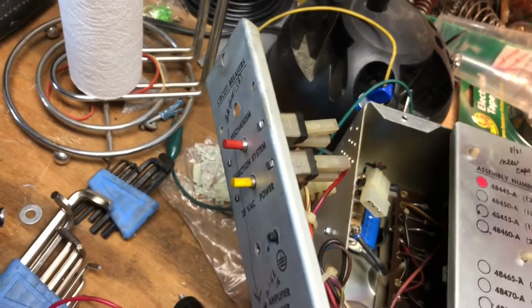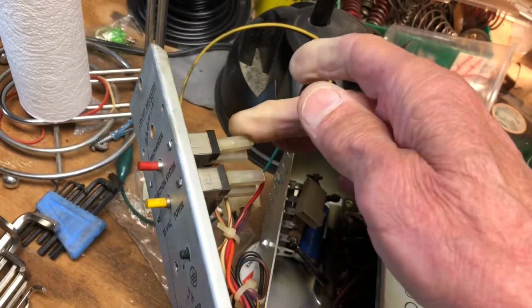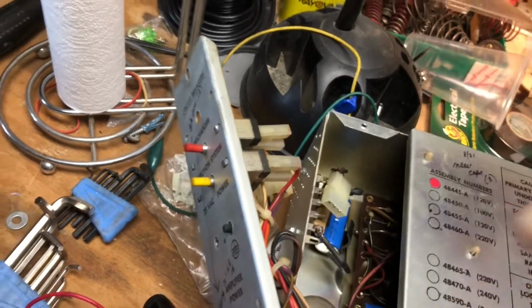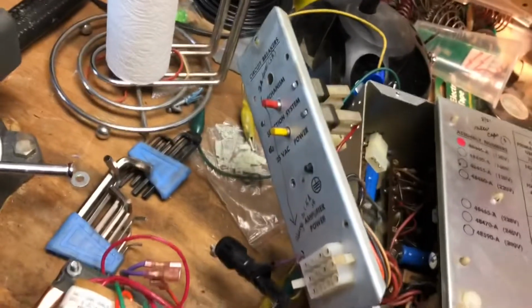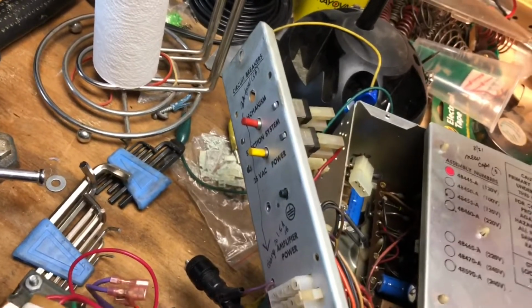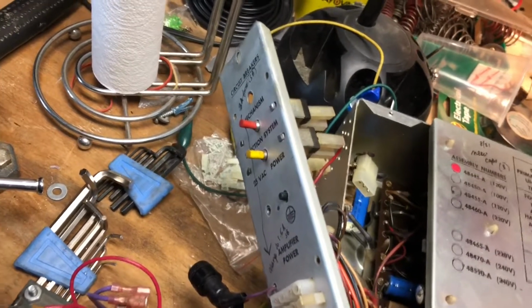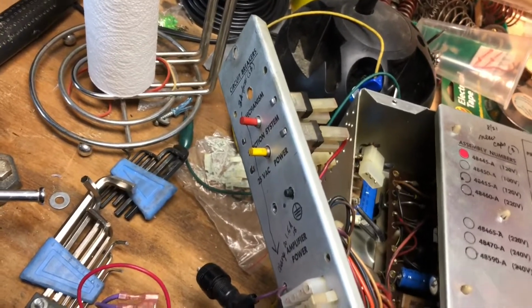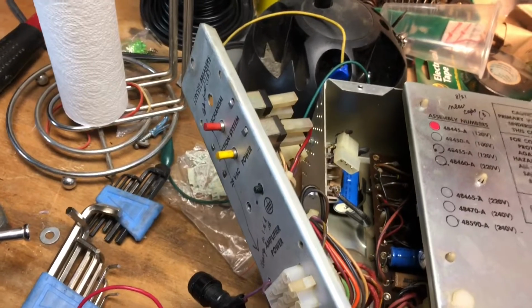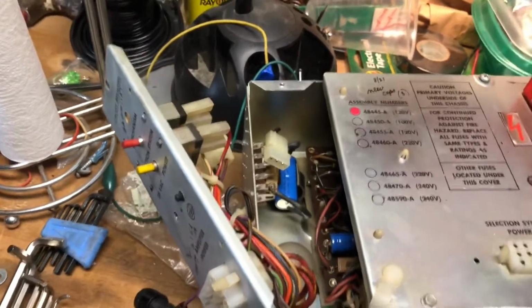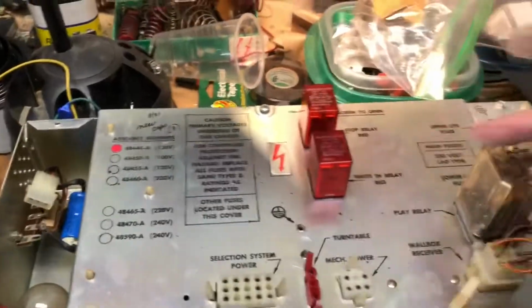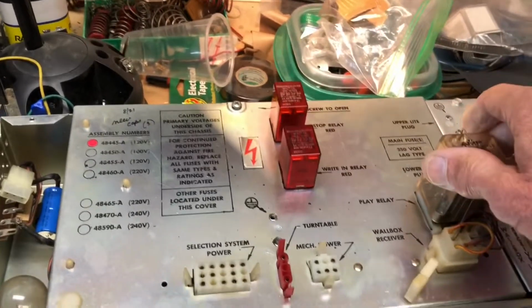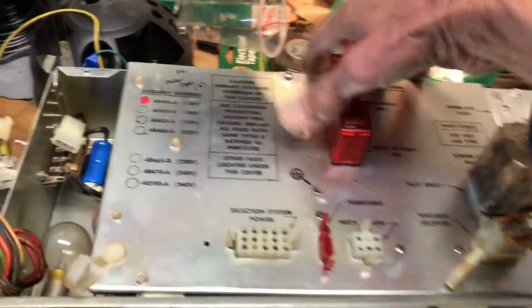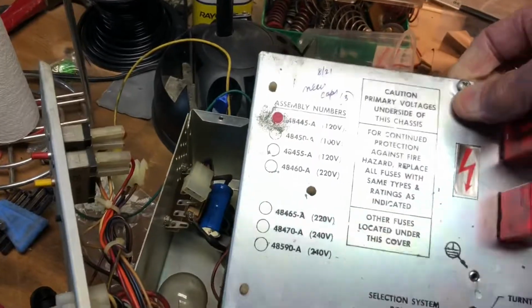So if you test across the 2 leads there, take these covers off, you should get some resistance of the circuit. And then when you press the button, it should open up. If that does not happen, then you're going to have to replace that circuit breaker. These relays are all described in the manual. I won't go into that any further, but I do want to show the inside of this.